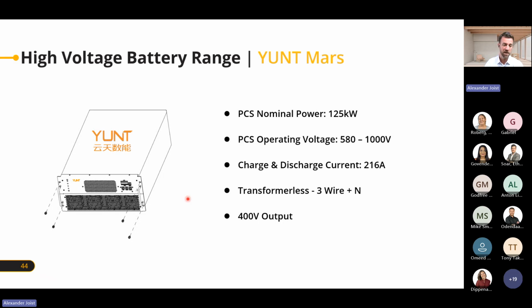If we have very extreme unbalanced loads and high startup currents on certain phases, this will damage the PCS long term, because obviously the transformer balances out the phases, and in this way brings a much more equal draw from the PCS. But if we have unbalanced loads and they're very high, with very high startup currents on a single phase of a 3-phase system, then this will damage the PCS.